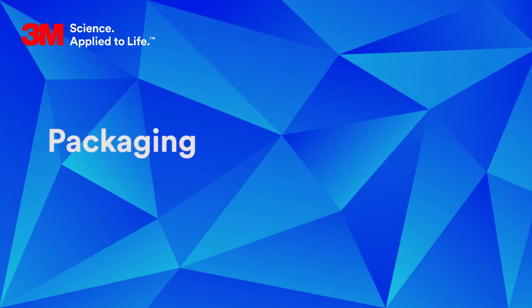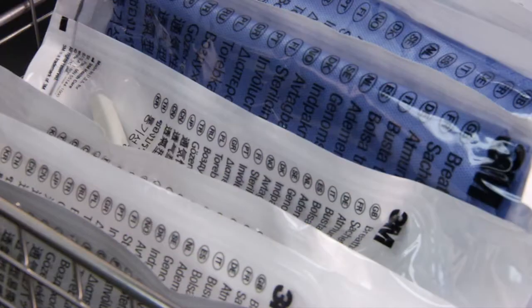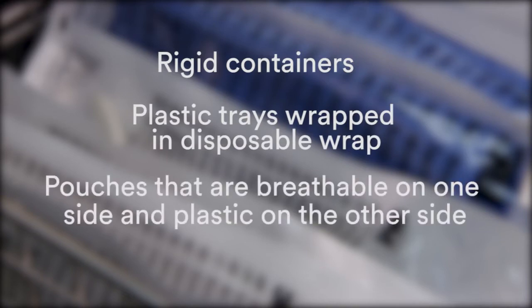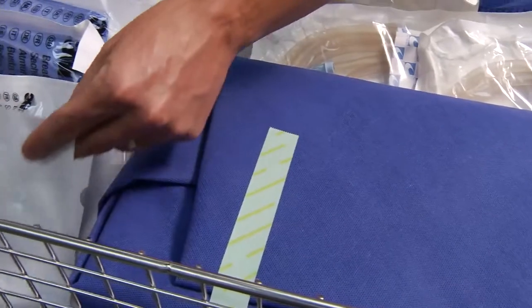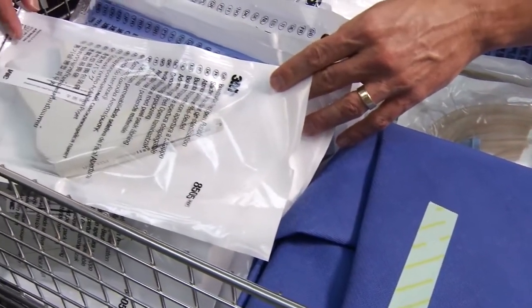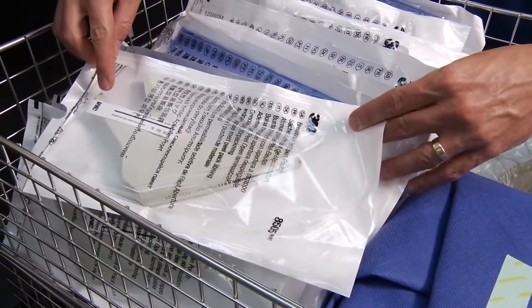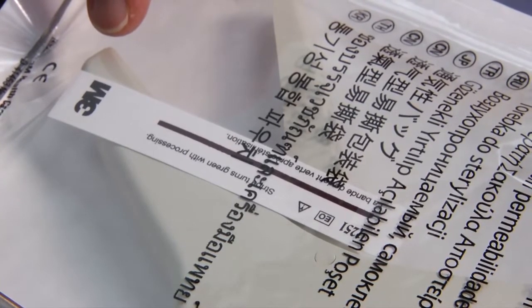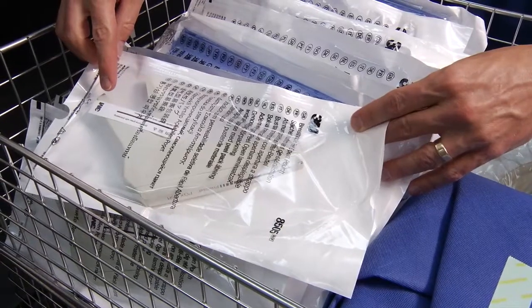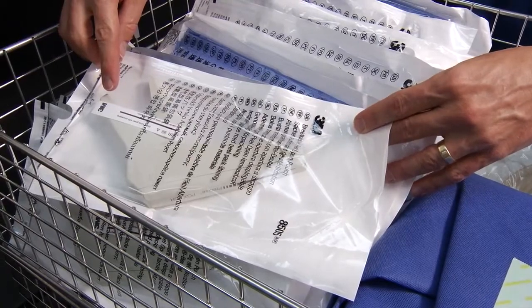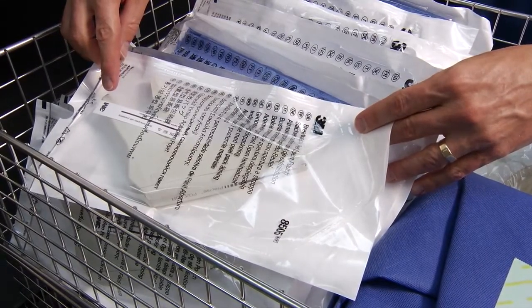There is a wide range of packaging available for use with this GS series sterilizer. For example, rigid containers, plastic trays wrapped in disposable wrap, pouches that are breathable on one side and plastic on the other side, and muslin. For healthcare applications, place a minimum of 1 ethylene oxide chemical indicator inside each container, wrap tray, or pouch. Reference the packaging manufacturer's instructions for use for complete instructions for proper chemical indicator placement.